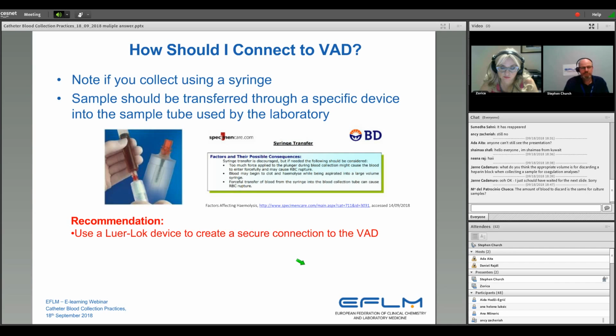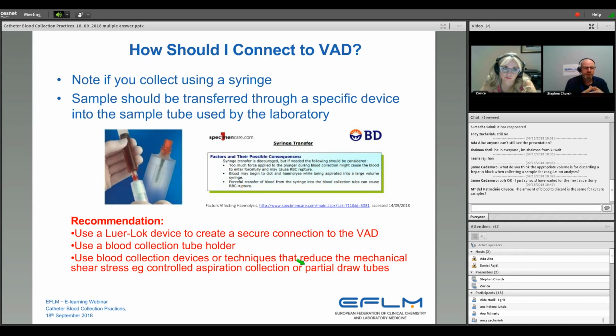So what's our final recommendation? Use a locking device to create a secure connection to the vascular access device. Use a blood collection tube holder, so make sure the tube is centralized, and use blood collection devices or techniques that reduce that shear stress, whether that's through a controlled aspiration or the use of partial draw tubes. And always transfer from a syringe to the laboratory sample tube with an appropriate transfer device.